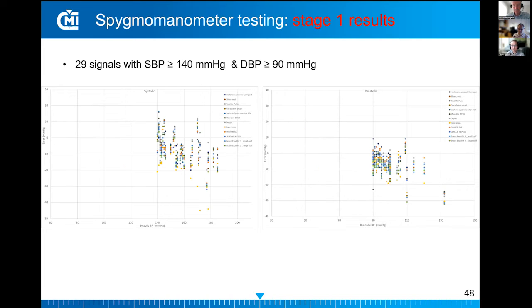If we look at the other half of the blood pressure range, we can see that in the hypertension region, there are devices that perform well, yet there are more signals that are outside the region of this plus minus 10 millimeters of mercury. And the most critical situation seems to be that the devices seem to underestimate the blood pressure, which could have, if used in a clinical setup, dire consequences. If we combine more signals with a region, not with "and" but with "or", then we can get a better view of the tested results.